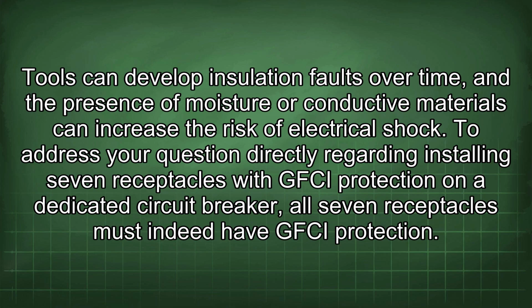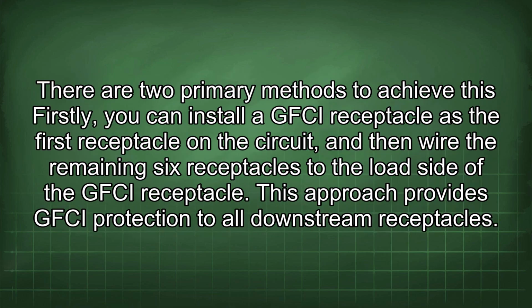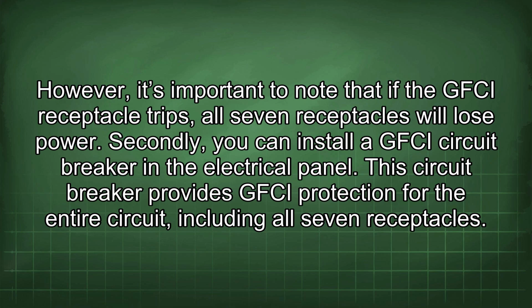electrical shock. To address your question directly regarding installing 7 receptacles with GFCI protection on a dedicated circuit breaker, all 7 receptacles must indeed have GFCI protection. There are 2 primary methods to achieve this. Firstly, you can install a GFCI receptacle as the first receptacle on the circuit, and then wire the remaining 6 receptacles to the load side of the GFCI receptacle. This approach provides GFCI protection to all downstream receptacles. However, it's important to note that if the GFCI receptacle trips, all 7 receptacles will lose power.